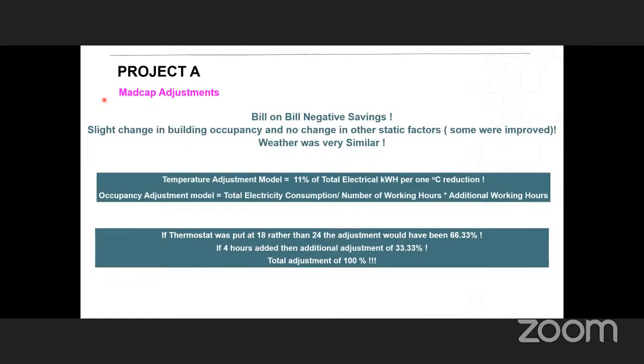This was a case of bill-on-bill negative savings. The issue is that the client was seeing those bills and comparing year on year - they had zero savings, or actually negative savings. The ESCO was saying, well, there have been some changes in the building, and this is why we're not getting the savings. Looking at what the client was saying, they said we didn't have any change in occupancy - it's a very basic change, maybe we've added a couple more employees, but that was nothing drastic.